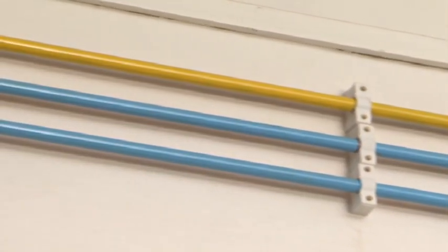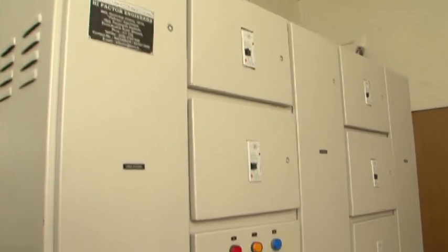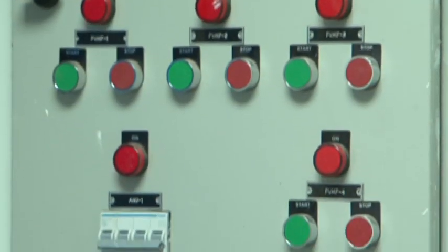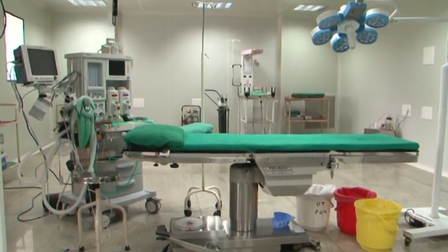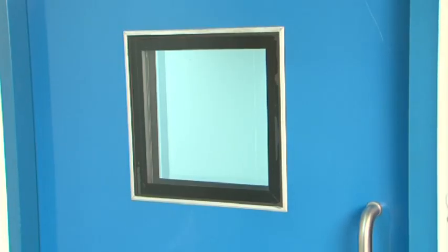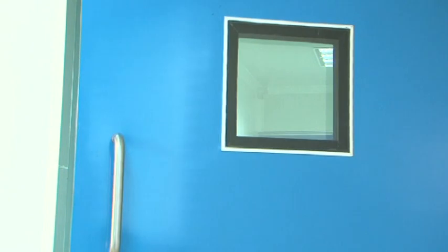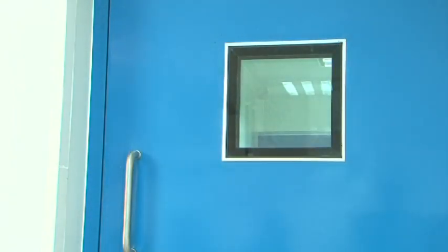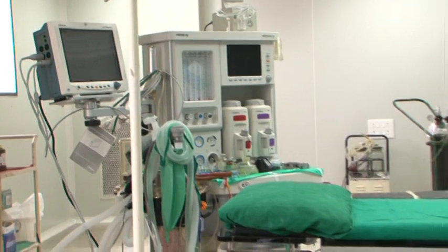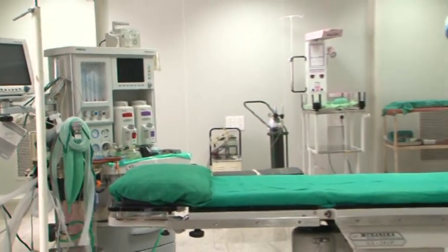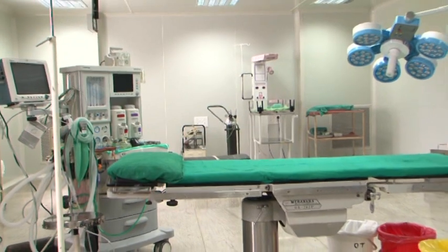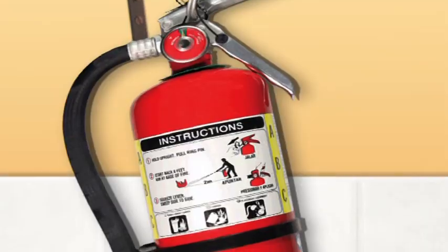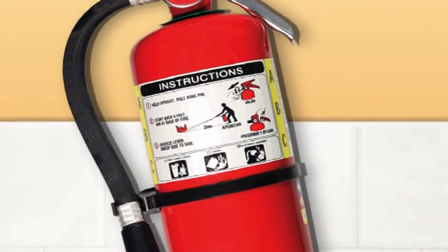The operation theatre should be air-conditioned with all airtight or sealed doors and windows. Arrangements to be done for piped suction and medical gases, electric supply, heating, air conditioning and ventilation of the operation theatre. Doors should be single panel, sliding or double acting, openable from both sides with a glass see-through panel. Only essential furniture and equipment to be used for surgeries should be allowed inside the operation theatre. Fire protection measures should be in place at strategic points.